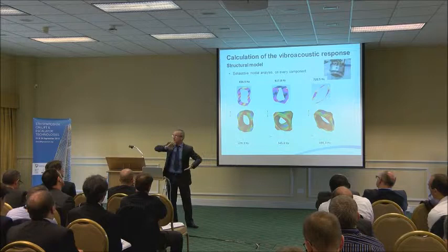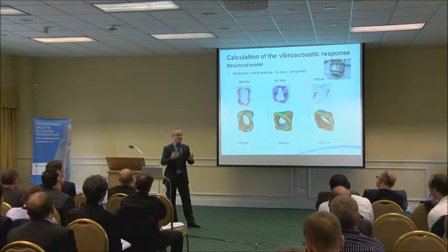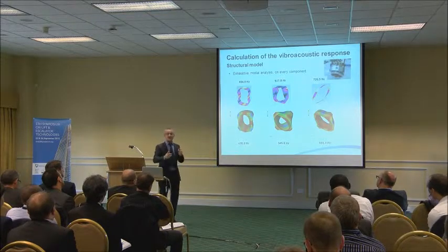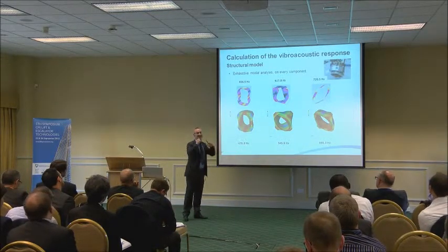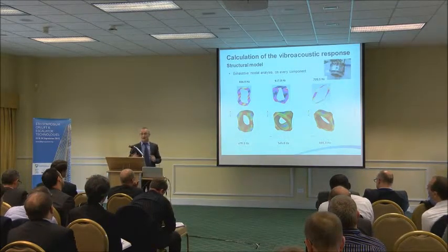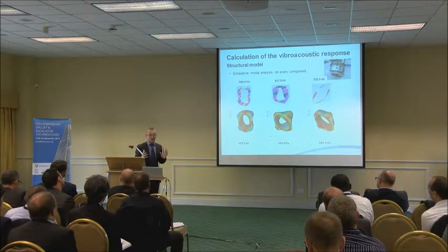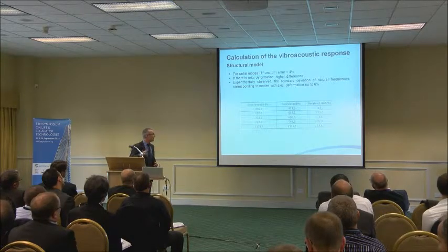This is because of the clamping pressure applied at the moment of manufacturing; it is never the same. So whenever we want to update our model, we look more at the radial modes than the others. We have done this with all the components of the machine, and at the final step with the whole machine. That is more complex, and it is more difficult to identify all the modes.